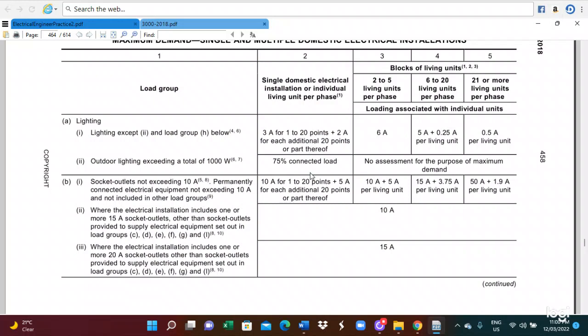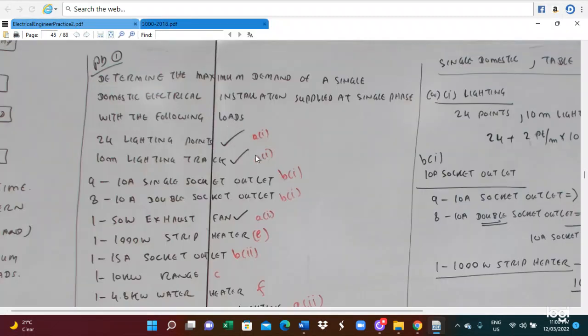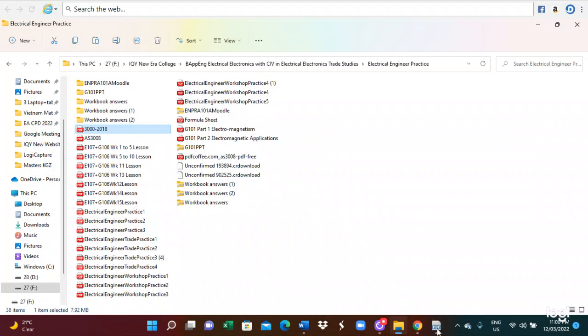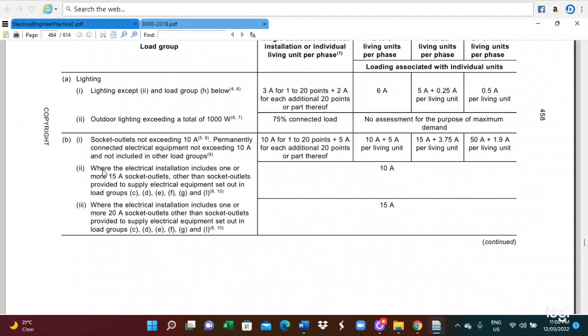Then you have to see how many light points there are. Firstly, we have 24 lighting points, which are in load group A1. For the lighting, the load group is A1. In the case of 1 to 20 points, you take 3 amperes, and for every additional 20 points you add 2 amperes. Because we have 24 lighting points, we refer to load group A1. Their rule is that for 1 to 20 points we take 3 amperes, and for every additional 20 points we add 2 amperes.